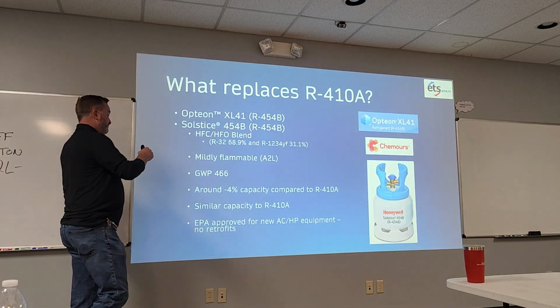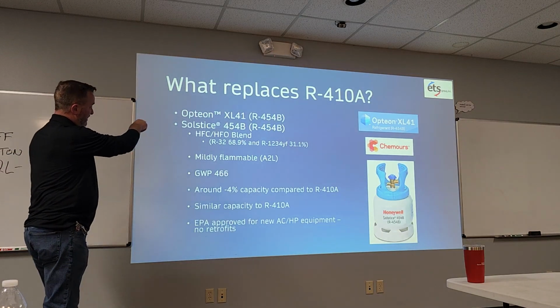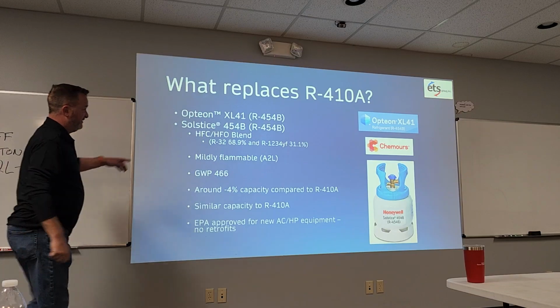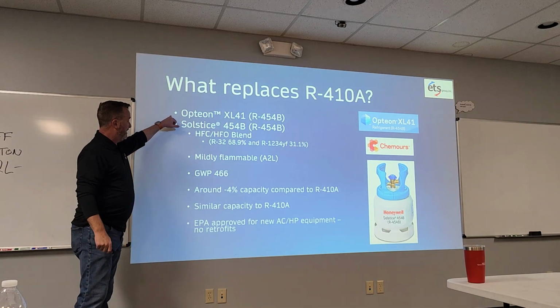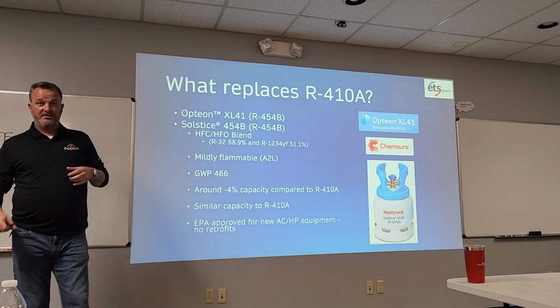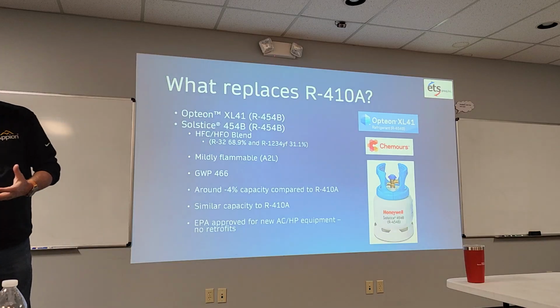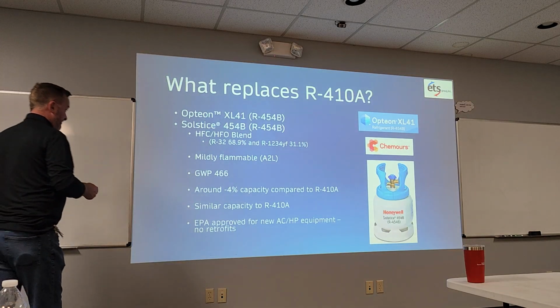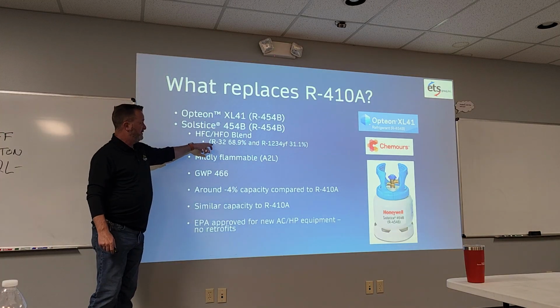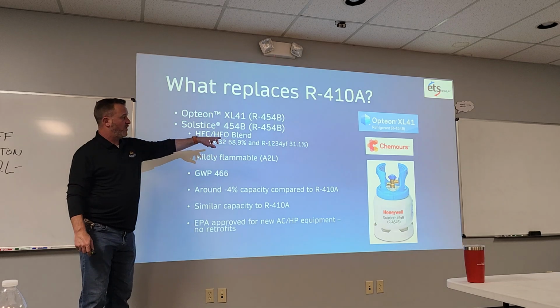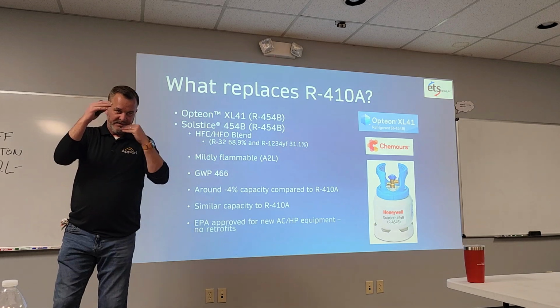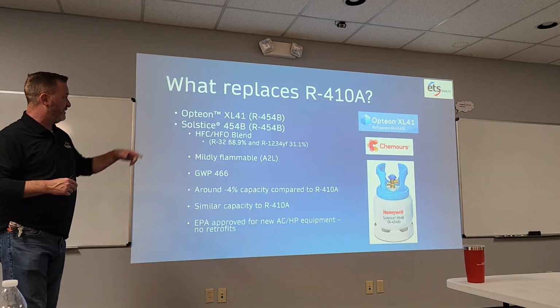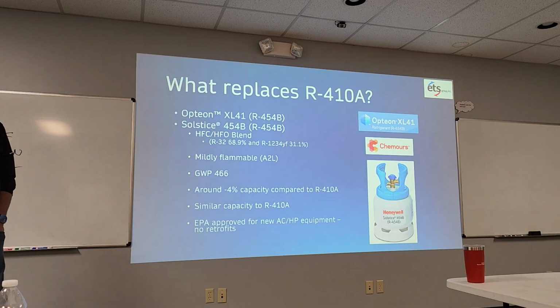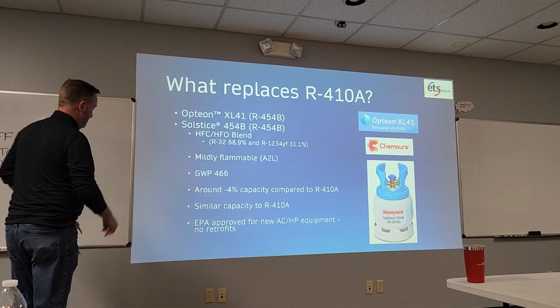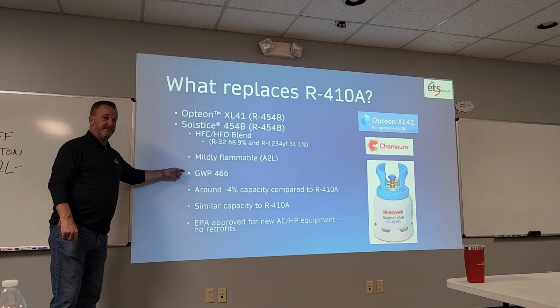So the next one, you've got the Opteon product and the Solstice product. Opteon is Chemours, the old DuPont. Solstice is Honeywell. They're going to be the manufacturers of 454B. It's a blend, so you've got 32 at about 70% and 1234yf at about 30%, a little different, 68.9 and 31.1 exactly. It's mildly flammable, and this one's got a GWP of 466.